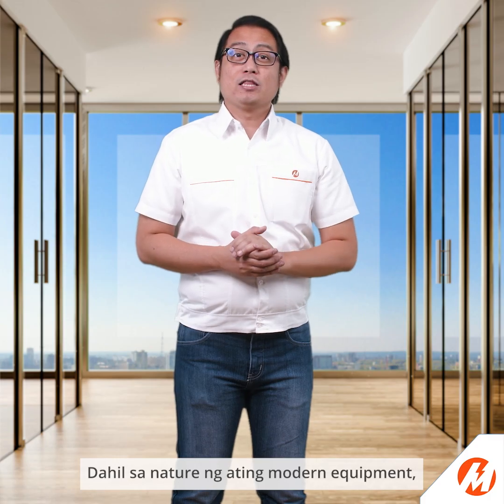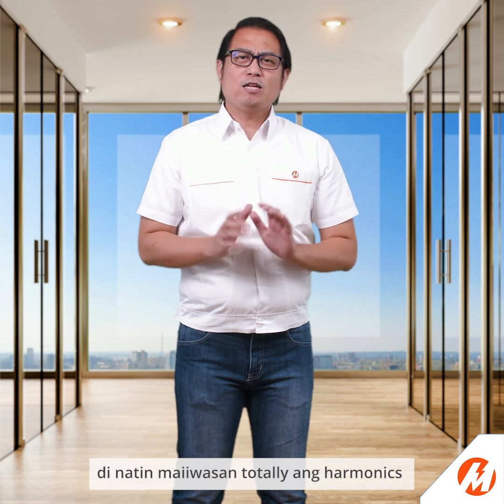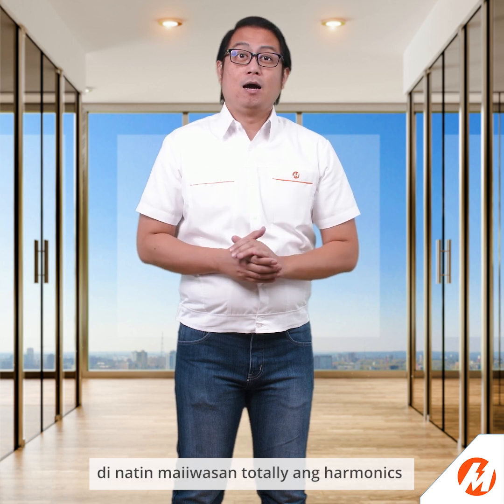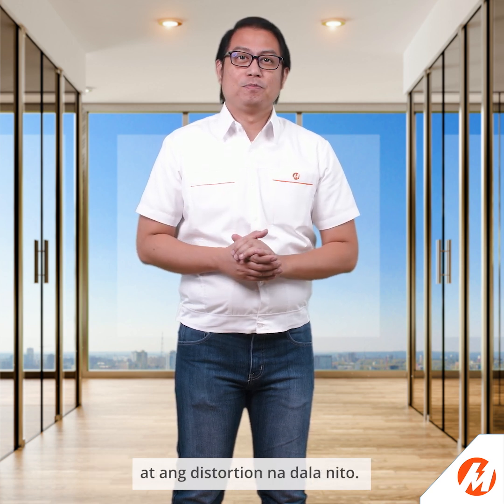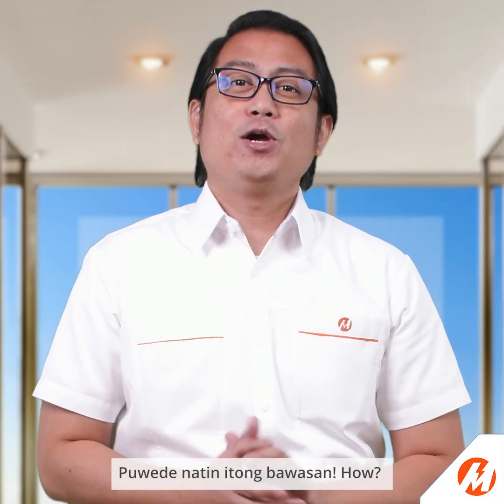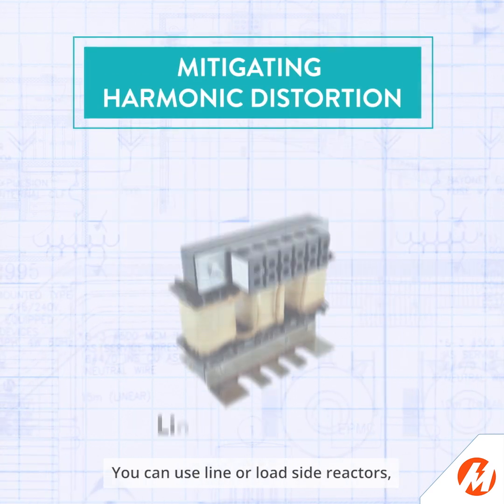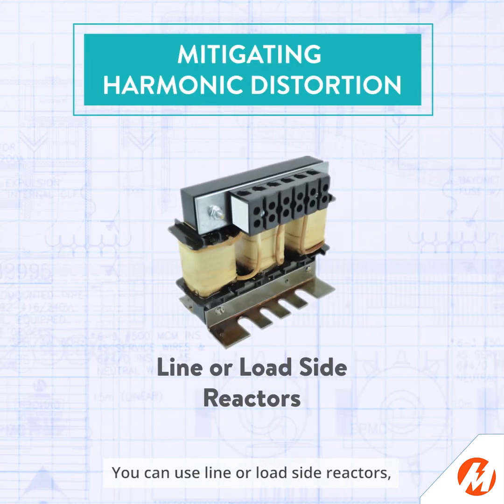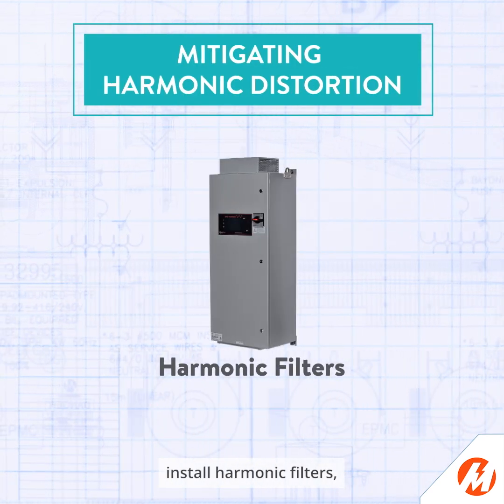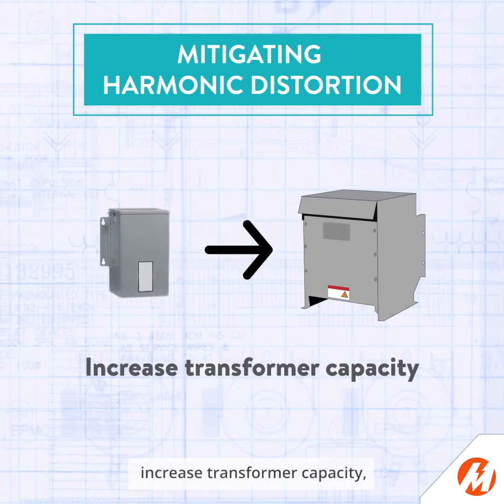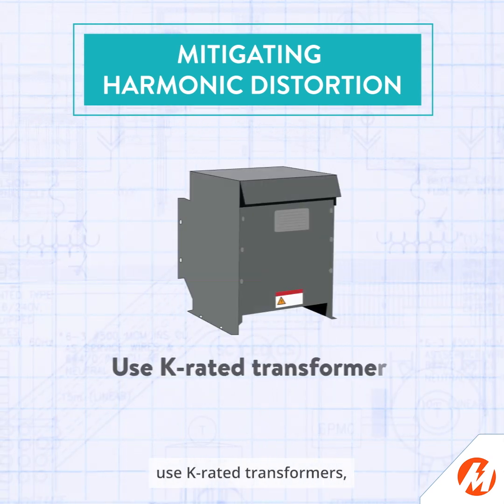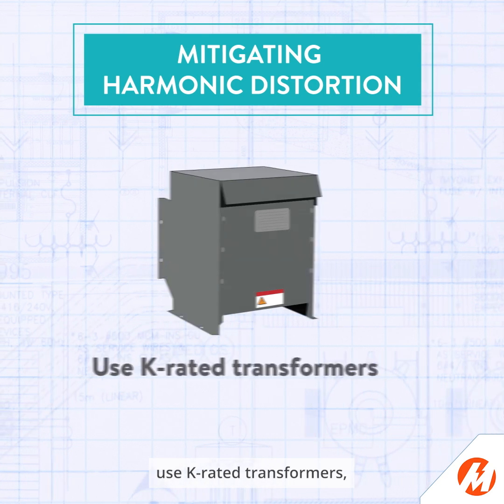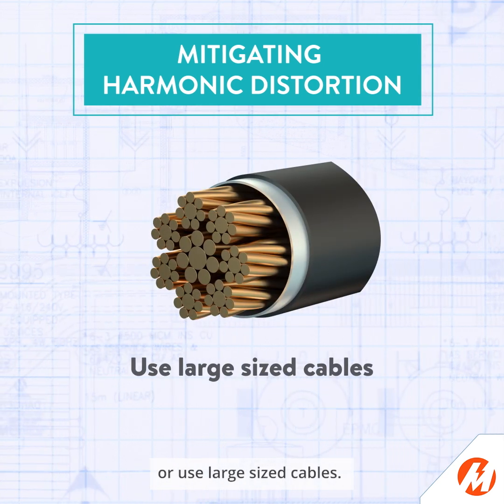Dahil sa nature ng ating modern equipment, di natin maiiwasan totally ang harmonics at ang distortion na dala nito. But pwede natin itong bawasan. How? You can use line or load side reactors, install harmonic filters, increase transformer capacity, use K-rated transformers, or use large-sized cables.